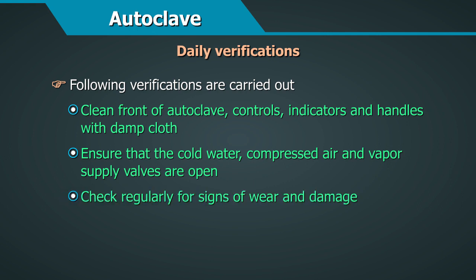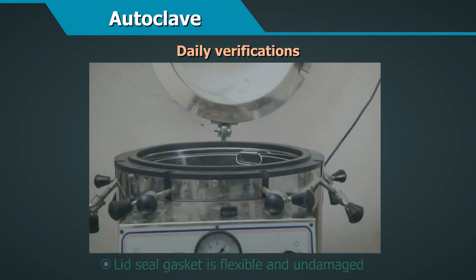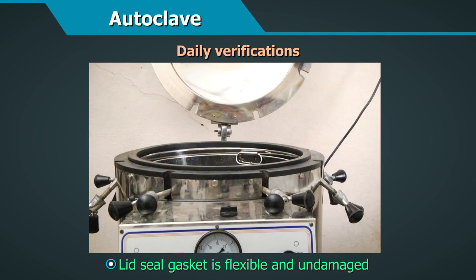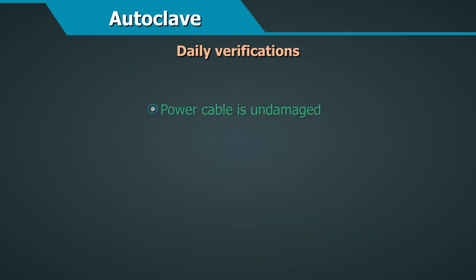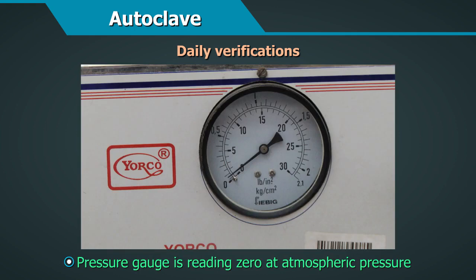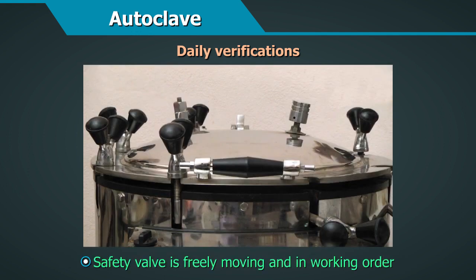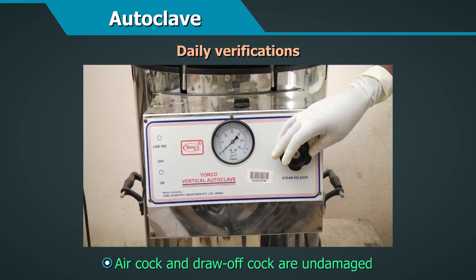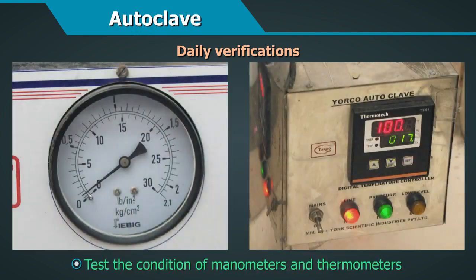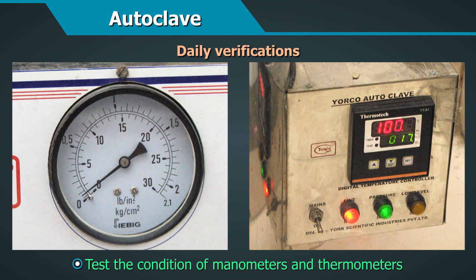Check regularly for signs of wear and damage. Examine particularly whether the lid seal gasket is flexible and undamaged and is not allowing steam to escape from the lid. The power cable is undamaged. The pressure gauge is in working order and reading 0 at atmospheric pressure. The safety valve is freely moving and in working order. The air cock and the draw-off cock are undamaged and working correctly with no leakage from seals. Test the condition of manometers and thermometers.